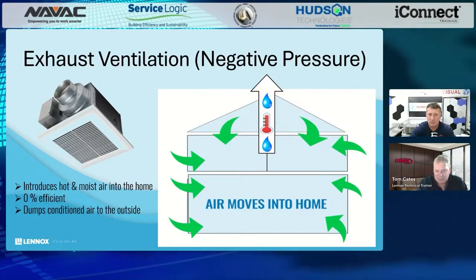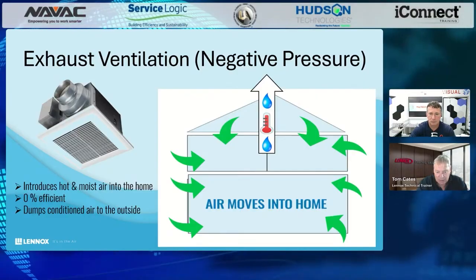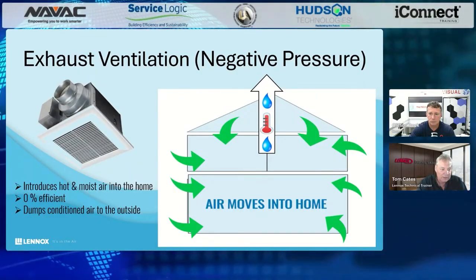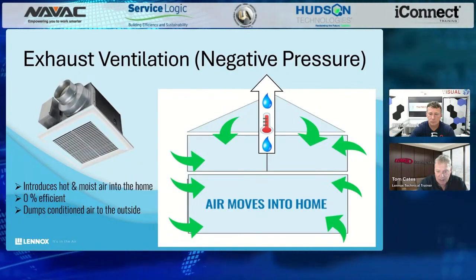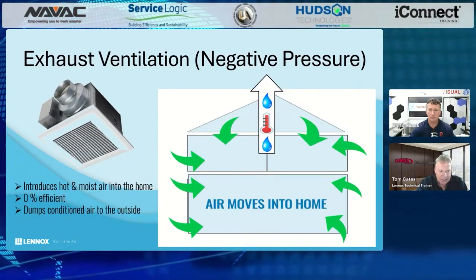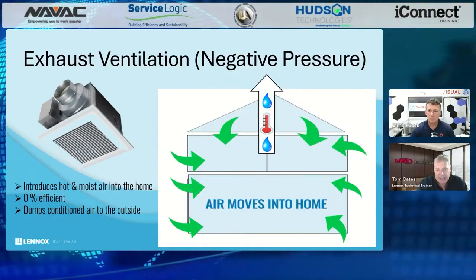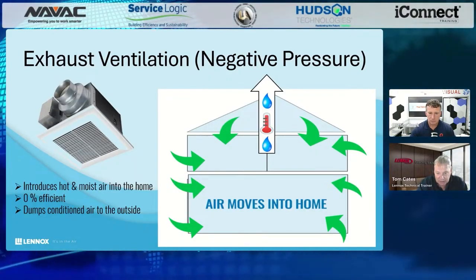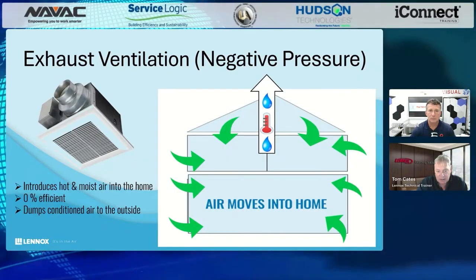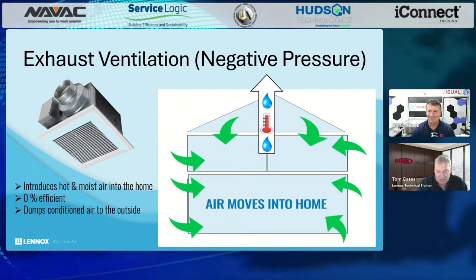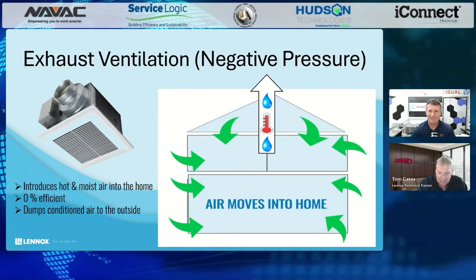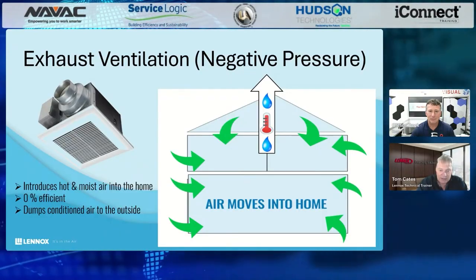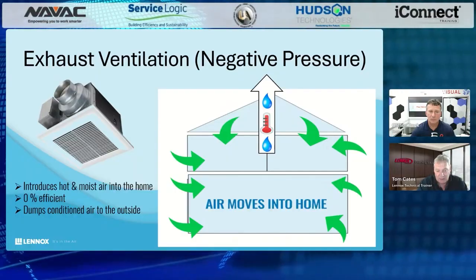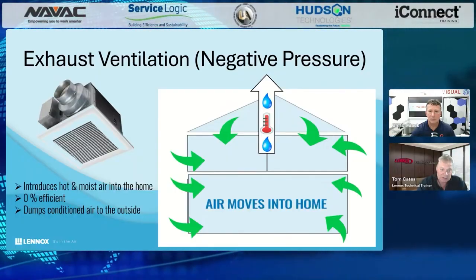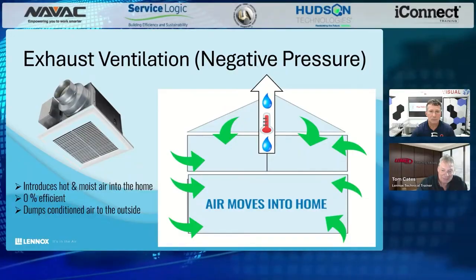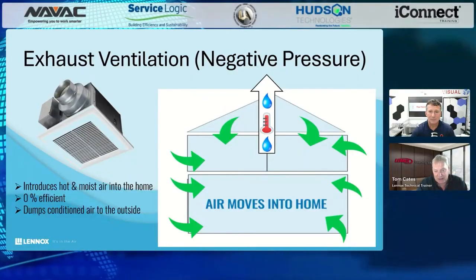Again, what I talked about, the bathroom fan is removing the air from within the building at a rate at which it was designed for, 50 CFM, 90 CFM, maybe 110 CFM. They come in all kinds of different sizes. But what it's really doing is creating a negative pressure imbalance within the building. And because of that negative pressure imbalance, Mother Nature always wants to come back to a balance. So what goes out must come in. Now, the looser or the tighter your house is will influence the amount of air movement that can occur across your building, and the size and the capability of your fan will influence how much air can also move, right?